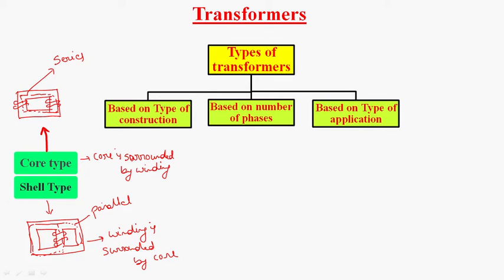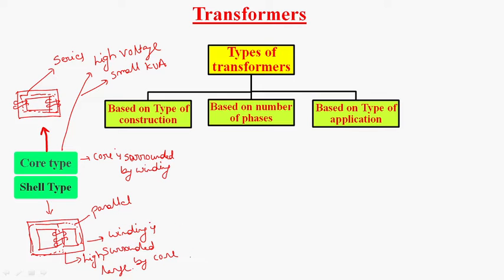In general, core type transformers are most economical for high voltage applications and are mostly used for small KVA rating. Whereas shell type transformers are economical for high current and large KVA rating.